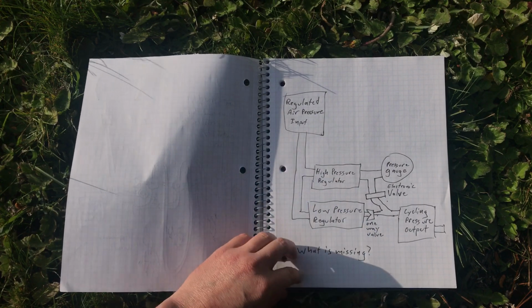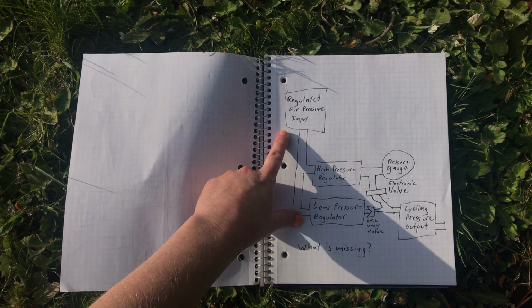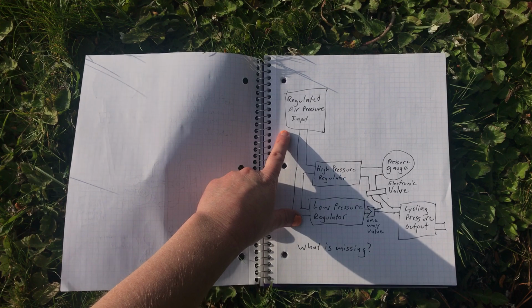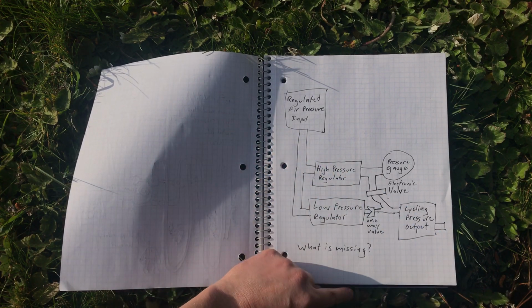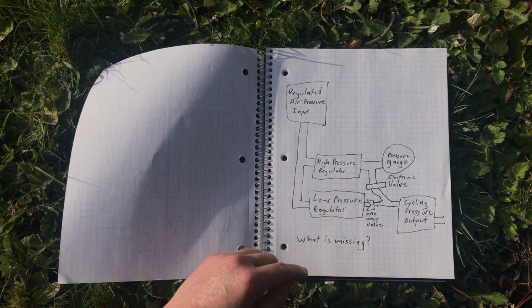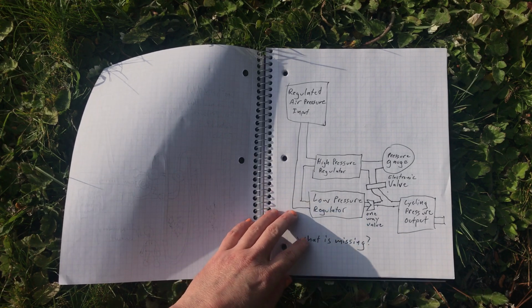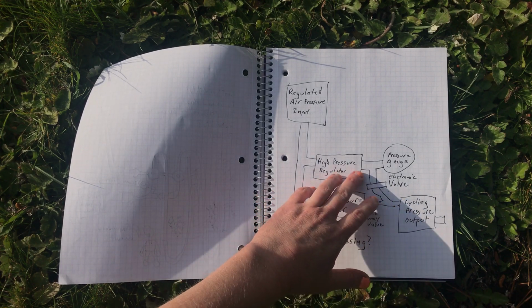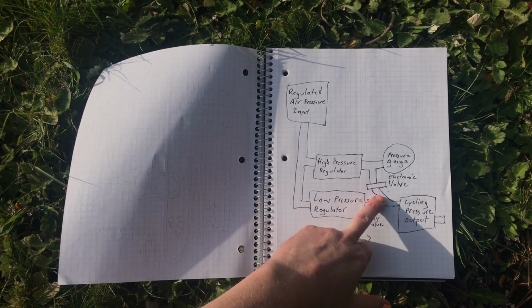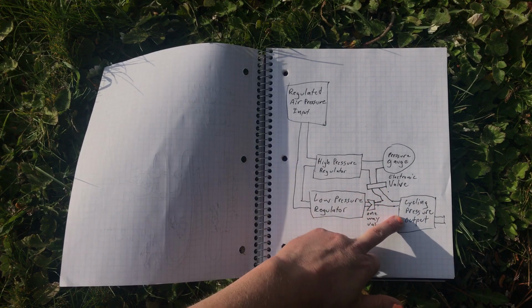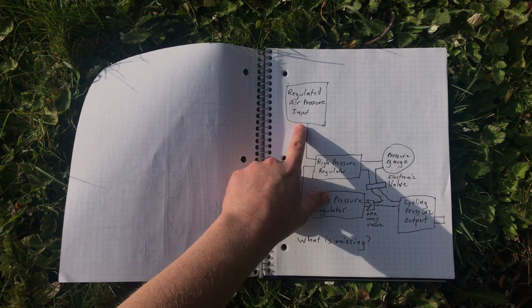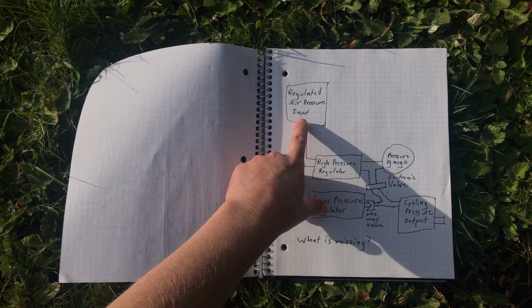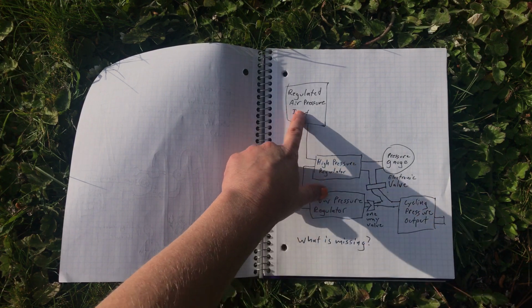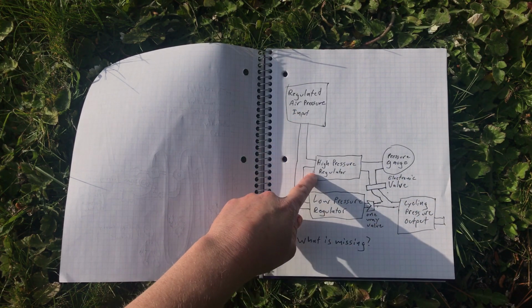Essentially, what I'm talking about in this system diagram is that you would first start with regulated air pressure input. Now, this may seem counterintuitive, but my understanding from the research is that actually the ventilators would provide simply a high pressure and a low pressure, which would cycle with an electronic valve. But no negative pressures are needed, which is why a simple air compressor with a pressure tank and a pressure regulator would be all that's needed to feed into this device.